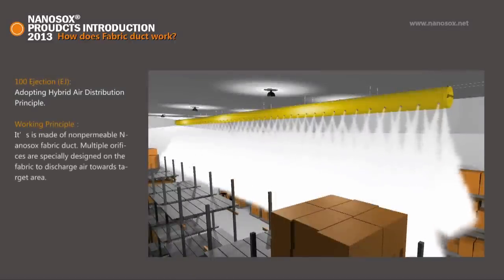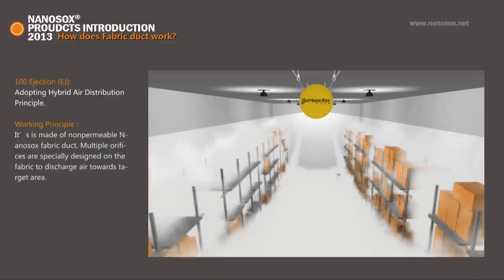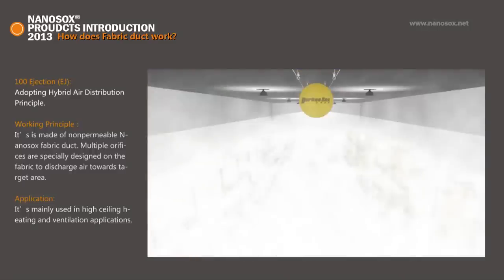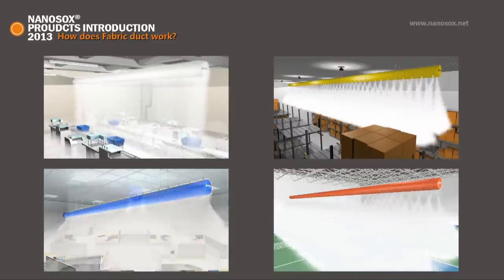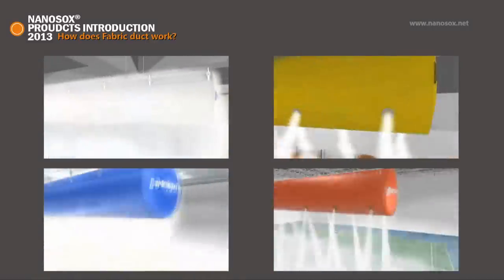100% Ejection EJ: It is made of non-permeable Nanosox fabric. Multiple orifices are specially designed on the fabric to discharge air towards the target area. It is mainly used in high ceiling heating and ventilation applications. Fabric duct is custom designed according to different airflow and static pressure of the air conditioning unit, using fabric of different permeability and engineered orifices to match the equipment.